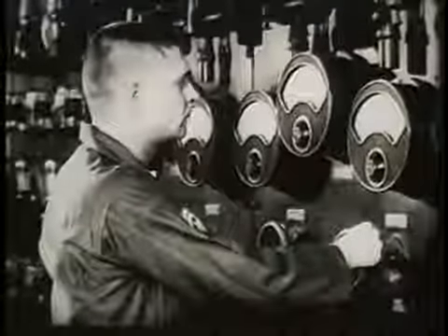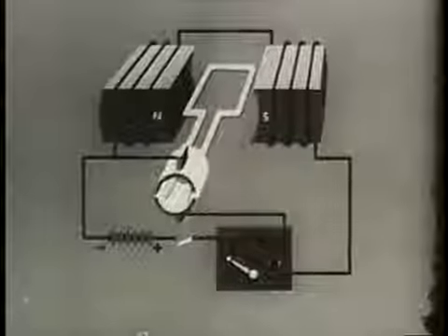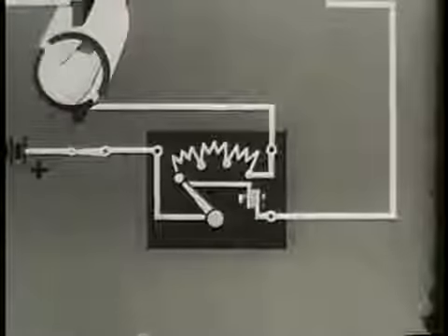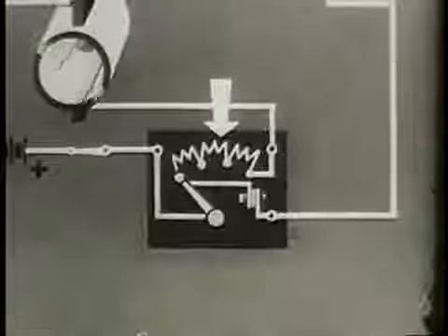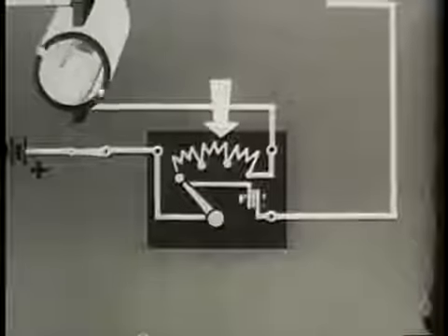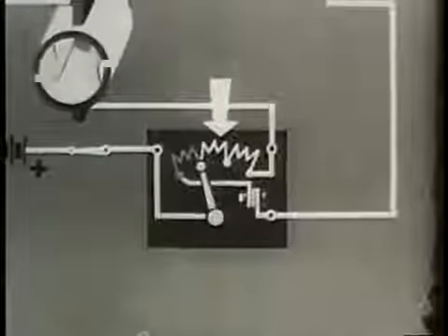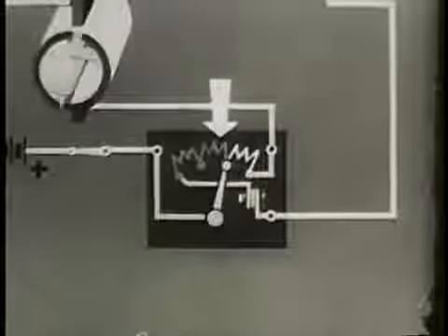When starting large motors, the problem exists of limiting current through the rotor windings until a CEMF can be built up. If the full current is applied before the CEMF develops, it may burn out the rotor windings. Starting boxes are used with DC motors in order to avoid this application of current before the CEMF is built up. Here is a basic shunt motor with its starting box. In the starting position, the circuit to the rotor windings is closed through a series of large resistance coils. As the lever of the switch is moved, rotor speed and CEMF build up gradually, and the resistance coils are subsequently cut out until running speed has been reached.